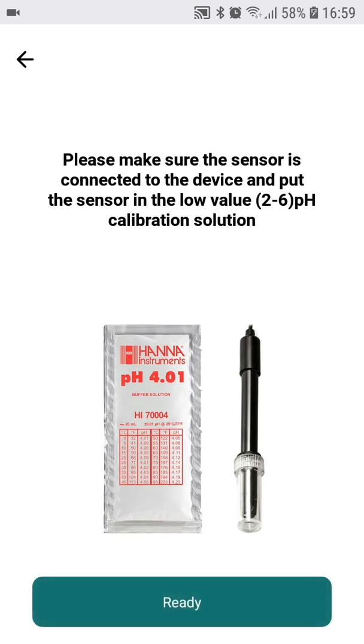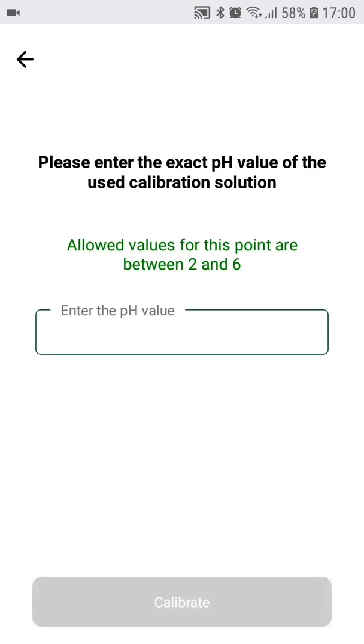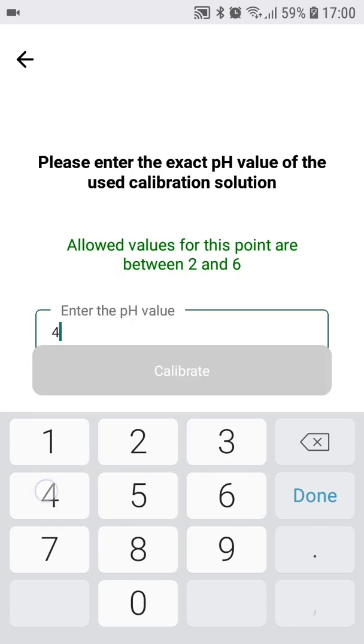One with pH 4 and the other one with pH 10. For future recalibration you can use any standard calibration solutions available. Before you start to calibrate the probe it is good to wash it with clean water just to get rid of the buffer solution used for storage of the probe. First we need to use the low pH calibration solution.